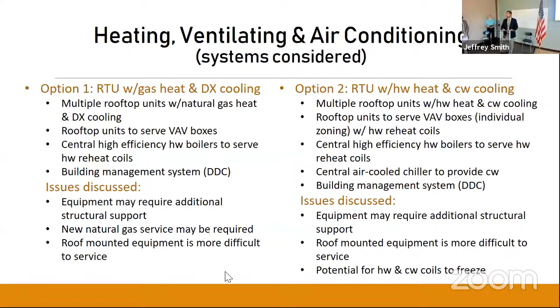Option number 2, again, looking at rooftop units, except this time looking at hot water coils and chilled water coils, which would put you back to a central plant with the hot water boilers and the chiller. Some of the items or issues that we discussed, again: the equipment may require additional structural support. Roof-mounted equipment is more difficult to service. And then you have a potential for hot water and chilled water coils exterior to the building to freeze. There are ways to remedy that. But if something happens with the antifreeze that you put in there, you don't get the right quantities, you can end up freezing a lot of equipment.